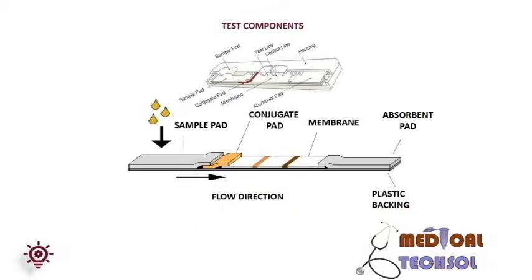The sample is added into the sample well of the cassette. It is absorbed by the sample pad. The sample migrates towards the conjugate pad by capillary action, combines with the conjugate, then moves towards the membrane and is immobilized on the test line and control line of the membrane, with the remainder absorbed by the absorbent pad.